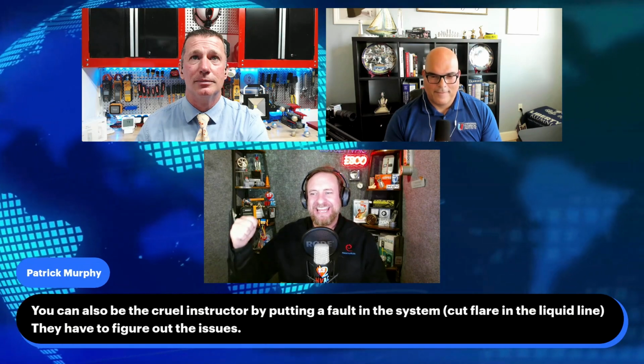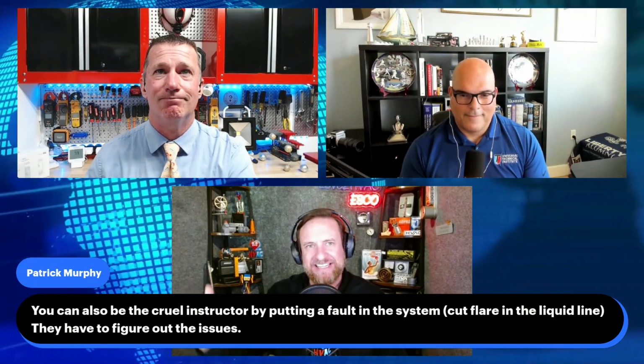By doing refrigeration, they can see what's happening with the temperature change, how it's affecting the saturated temperatures. Especially with the pump down cycle, they can see that pressure switch closing and how that's reacting to the contactor. With low ambient controls, they can see how we can bypass that, especially with a liquid receiver. If you have a powerful heat gun and heat it up with an infrared camera, they can see the oil level and refrigerant level in there, and then transfer that understanding to subcooling and what's happening in the condenser. It helps them really understand the importance of the bigger picture in the cycle, because we all get bad habits at some point in life.